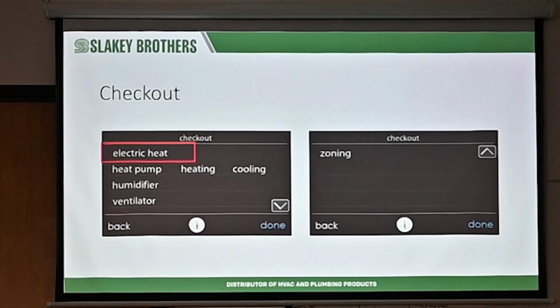Checkout. On the maintenance side, this is where I always teach my guys to go, to tell the AC to come on and keep it on, so you go out there and check it out, or if you just want to see why it faulted. So in the checkout, you see all the different modes that it can do. You can check out your zoning, you can test your zoning. You're going to turn on the electric heat strips with some airflow. This is a heat pump unit here, so you're going to turn on heating or cooling in the checkout mode.